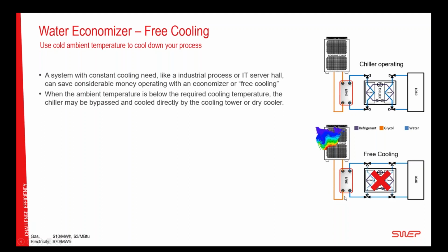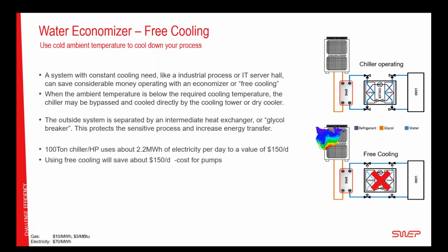Since the outside loop is typically operating with glycol, or if it's an open loop, it's not using glycol, but it's more dirty. Either way, if it's glycol or an open loop, you don't want to have glycol into the load side, and you don't want to have dirty open loop water into the server side. You need an efficient heat exchanger that can transfer the energy from the cold outside to the inside. And the economics here is very impressive.